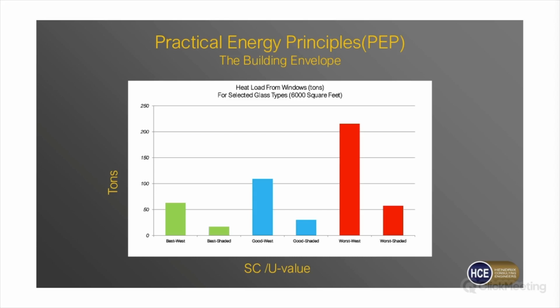Glass is a little more complicated to talk about since there are more variables. This is for a fixed amount of glass, 6,000 square feet, similar to a typical classroom wing. We've divided it into the best values for shading coefficient and U value in green, good values in blue, and really bad values in red. There are two bar graphs for each color because the load on windows changes quite a bit depending on orientation and whether or not they're shaded.